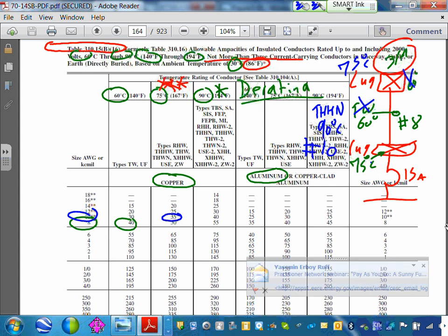Any comments, guys, about how to go, though? So your engineers, 99% of the time, are going to be in a 75-degree column. You specify the cables. We specify the cables. We're not electricians where things are shoved or thrown. We specify the THHN conductor all the time. Typically, guys, there's two insulation. They have THHN/THW. That's kind of the common insulation that we use. So why do we specify THHN/THW?